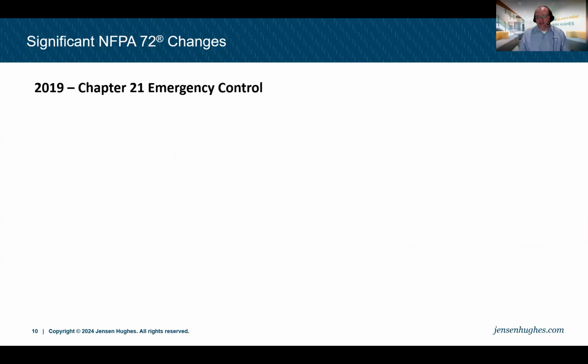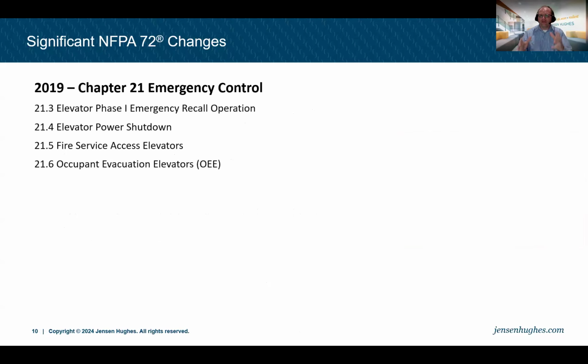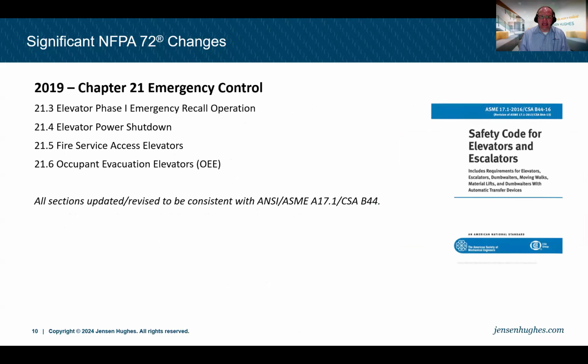Now, inside emergency control, which is Chapter 21, we had a significant change in the 2019 edition of NFPA 72, where all of these sections in NFPA 72 regarding elevators were updated to be consistent with ASME A17.1. Now, A17.1 is the safety code for elevators and escalators, specifically new elevators and escalators. And so all of these sections were reviewed by committees that kind of looked at NFPA 13 and NFPA 72 and A17.1, and they kind of came together and really solidified our interfaces with our elevator. So whether it's phase 1 emergency recall operation, whether we're shutting down the power for our elevators, all of that has been updated as of the 2019 edition, and we've seen it fairly consistently since then in NFPA 72.